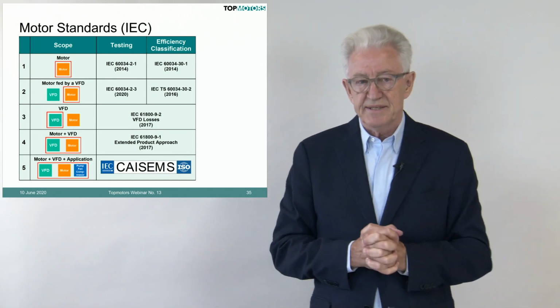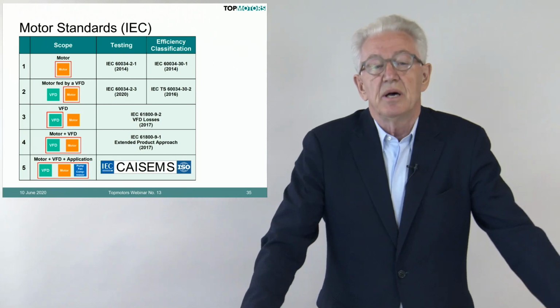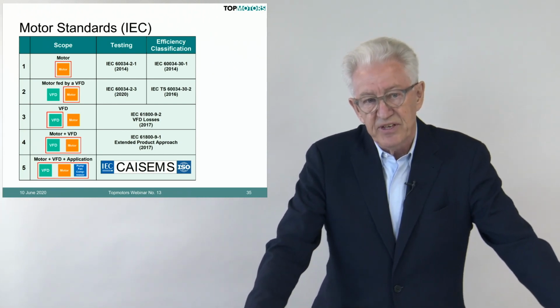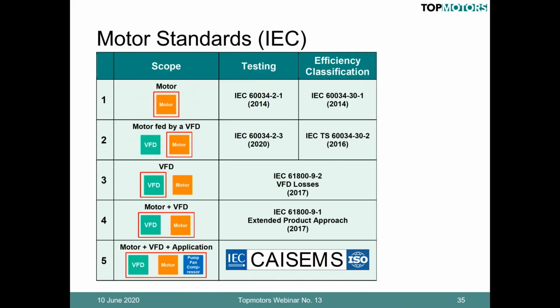When you look at the motor standards, the basic of the motor standards is just the motor. It has a testing standard and an efficiency classification. Then on the second line, you see a motor fed by a converter, by a variable frequency drive, has a separate testing standard and has a separate efficiency classification. Why is this needed? When you feed a motor from the grid with 50 hertz and the perfect sinus, you get what you expect in efficiency. When you feed it from a converter that uses pulse width modulation, you don't give it a nice sinus, but you give it a staggered sine feed for the voltage and the current. That means the motor losses are a little bit higher.